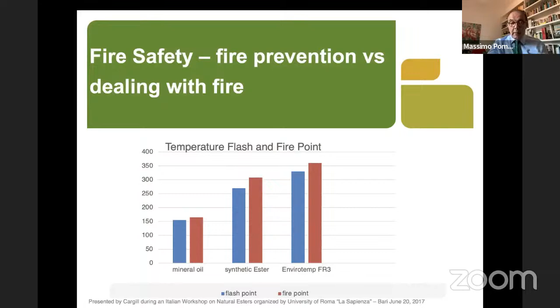It's important to look at the flash point, which is the temperature at which the vapor of the liquid starts to burn. On the left side of the graph, mineral oil's flash point is around 150 degrees. The flash point of natural ester is more than 300 degrees, more than double. This means the risk of fire using natural ester is much lower.